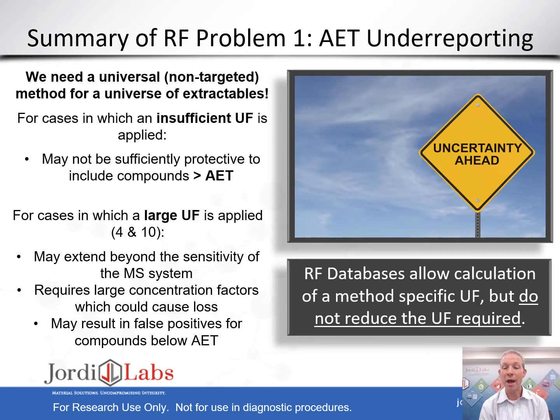So in summary of our RF problem number 1, which I will describe as AET underreporting, we can see that we need a universal method for analyzing extractables and leachables because we do not know in advance which kinds of compounds are going to be present. In other words, this is screening analysis. We don't have a subset of compounds we're looking for. We're just looking for anything that comes out of our device.